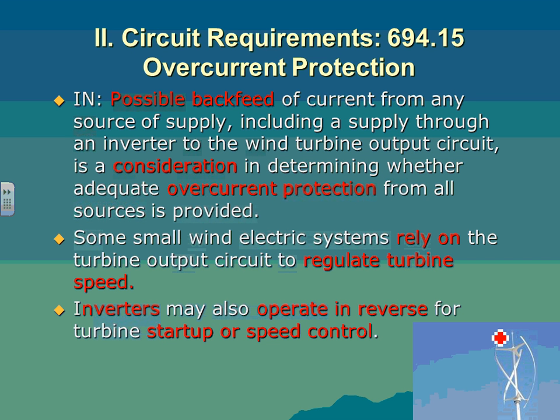And this is where some small wind electric systems rely on the turbine output circuit to regulate the turbine speed. What they do is take a sensor on the output and feed it back into the controller of the turbine to regulate the speed of the turbine, so it doesn't spin too fast. There's also a switch where you can shunt the system, bring it to a complete halt. So the inverter may also operate in reverse for turbine start up and speed control. That's where they talk about speed control in reverse. This is very typical also for bigger equipment.